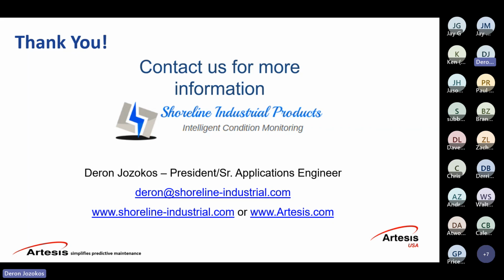Here's a question. Is a PC mandatory for the EMCM to work? Yes, it is. You have to have communication to the server so the software can show all of the data. Out of the EMCM, it does need constant communication. The EMCM itself does not store that data. It pre-processes everything, the waveforms and everything internally, and then sends out processed data. So it's very light as far as transmission, and sending the data to either the cloud through an LTE router. It's not going to bog down with gigabytes of data. On average, about 20 EMCMs going through one LTE cellular router would use maybe a gigabyte in a month. That's 20 units. So very light data, but it does need constant communication to the PC or the server.